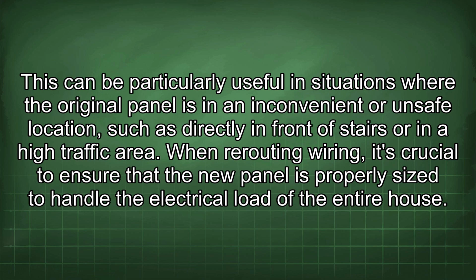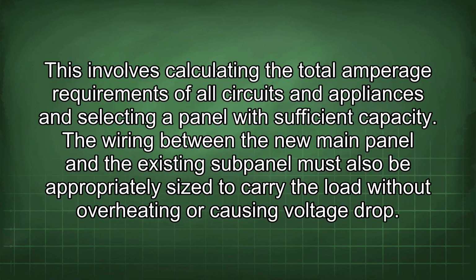When rerouting wiring, it's crucial to ensure that the new panel is properly sized to handle the electrical load of the entire house. This involves calculating the total amperage requirements of all circuits and appliances and selecting a panel with sufficient capacity. The wiring between the new main panel and the existing subpanel must also be appropriately sized to carry the load without overheating or causing voltage drop.